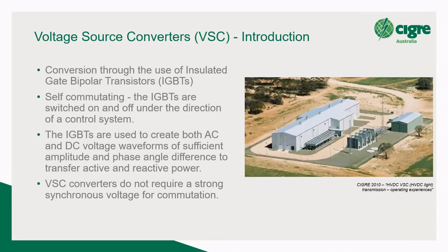So moving on to VSC. They use IGBTs, insulated gate bipolar transistors, self-commutating, as I mentioned. And the thing about the converters is they use IGBTs to create both an AC voltage waveform and a DC voltage waveform. And it needs to create its own AC waveform, whether it's a rectifier or an inverter, of sufficient amplitude and phase angle to allow active power and reactive power to flow. And I've got some formulas I'll show you in a second.